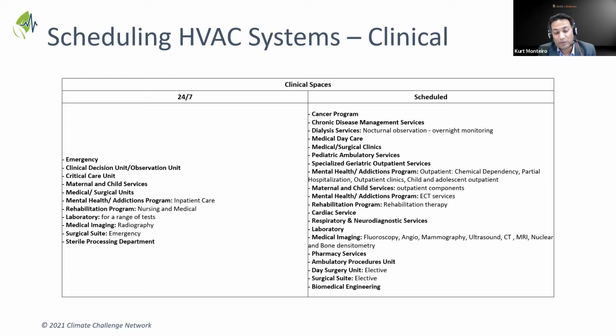On the infrastructure side, very early in the design, we looked at those departmental drawings, and when laying out our ductwork and distribution, we made sure we provided that level of granularity of control. So within a department you could have multiple sub-departments, and based on those you'd be able to cut off airflow, because some portions might operate three hours later than another, and so on. Our designers paid a lot of attention to that level of detail.